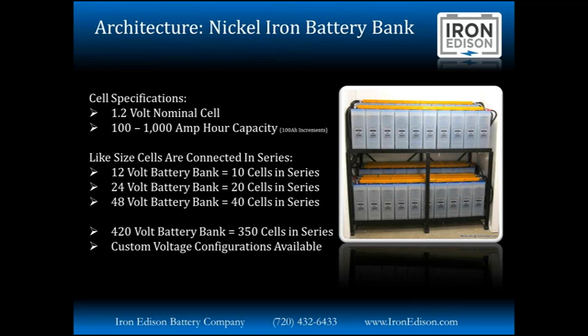The architecture of a nickel iron battery, it is actually a 1.2 volt nominal cell. Iron Edison offers nickel iron batteries from 100 amp hour up to a 1000 amp hour capacity in 100 amp hour increments. And what we do is we combine similar size cells in a series to create the battery bank voltage we need. So for a 12 volt nickel iron battery, you're actually going to have 10 individual cells in a single series. A 24 volt battery bank will have 20 cells in series, and a 48 volt, like you see in the picture here, is 40 individual batteries in a single series to create a 48 volt nominal battery bank.